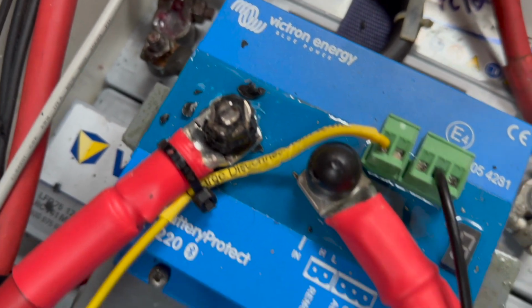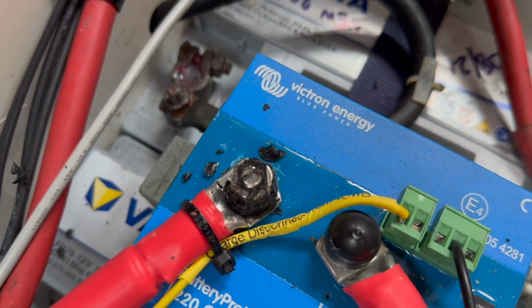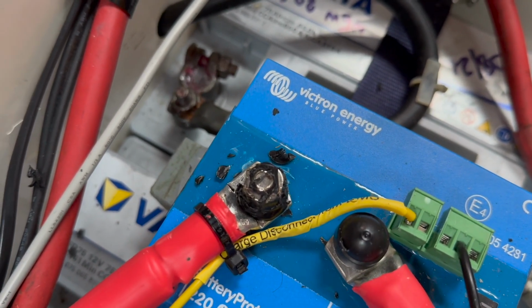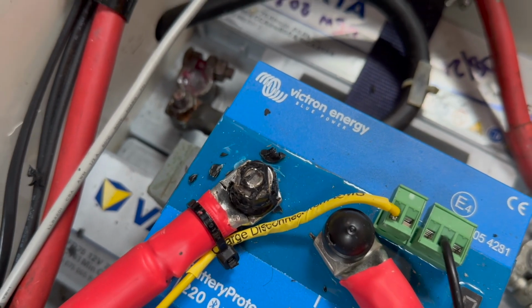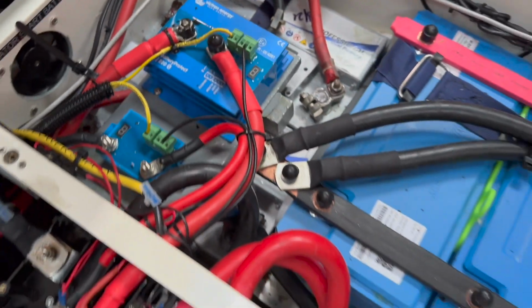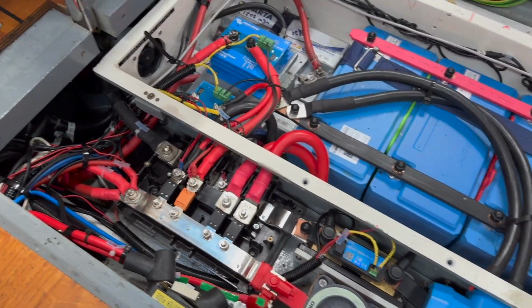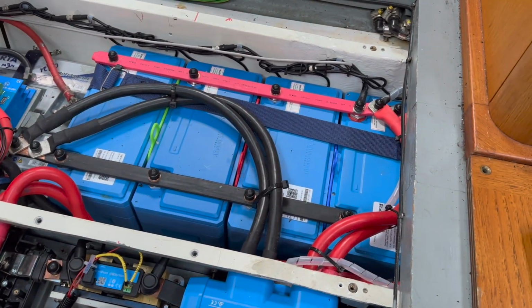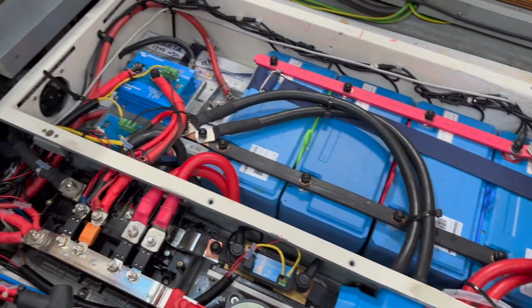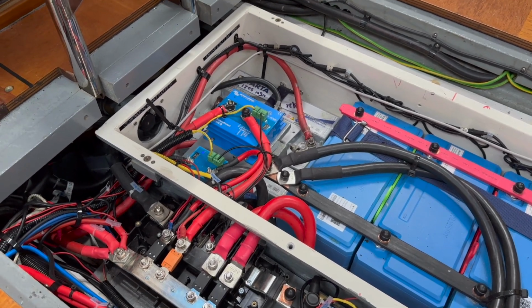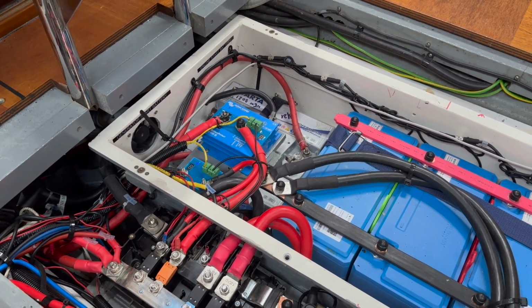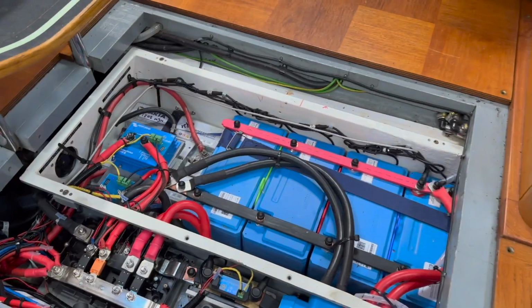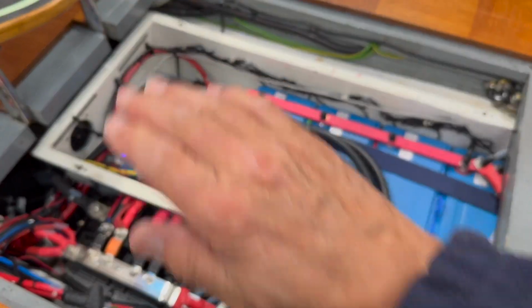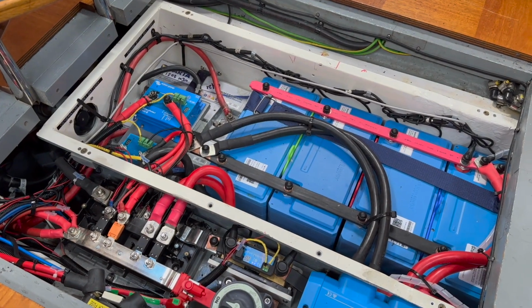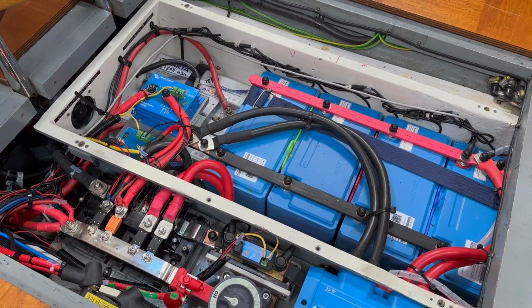So now I've got to fix that by taking off the nut, putting new nuts in, cleaning everything up, putting it back together again. And it's interesting because I've tested all these systems for heat on connectors and things - I do it quite regularly, but I hadn't actually done this while we were underway because it's difficult to get the floor panel out, and there's a lid that goes across here and all sorts of plastic covers to protect everything. It's quite difficult to do that when you're under passage.